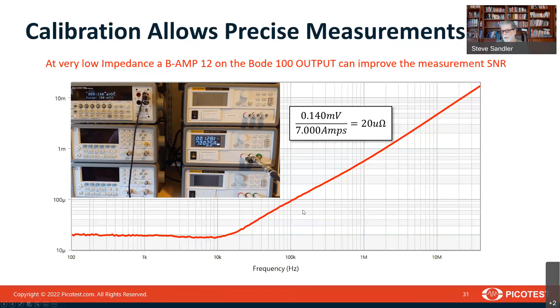Achieving that can be really difficult, but one of the things that I highlighted in the paper is there's only one way for us to improve the signal to noise ratio in this measurement. We can't put a preamplifier on the right side of the measurement, on the receiver. That'll just amplify the noise that's on the board. So everything gets elevated, both the signal and the noise. It doesn't make any improvement in the signal to noise. The only way to improve signal to noise is to put a source power amplifier on the output. And so we use the BAMP12 for this measurement. That increases the source level quite a bit. That improves the dynamic range, allows us to make better measurements. We put the coaxial isolator first to improve the measurement, and then we do the calibration, and now we can do an accurate measurement of 20 microhms.